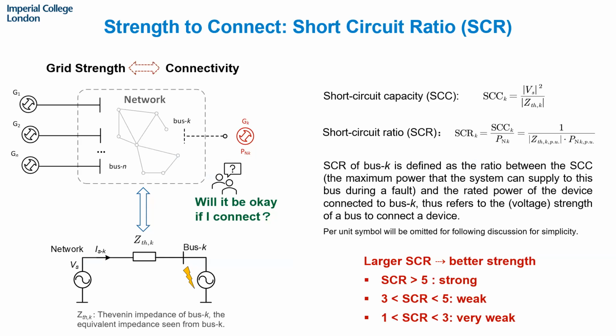When we are going to connect a new device, say at bus K here, we need to stand at bus K, look at the grid, compare the power, and see if it will be safe for us to connect this new device to this bus. Then we need an assessment of the grid strength.